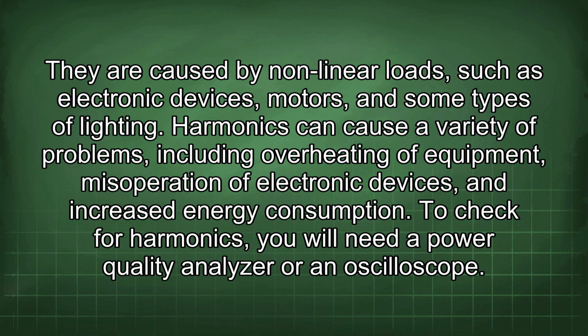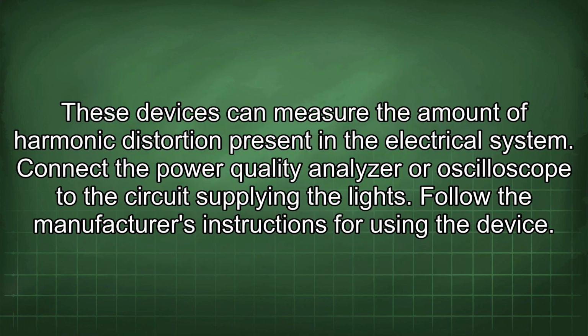Harmonics can cause a variety of problems, including overheating of equipment, misoperation of electronic devices, and increased energy consumption. To check for harmonics, you will need a power quality analyzer or an oscilloscope. These devices can measure the amount of harmonic distortion present in the electrical system. Connect the power quality analyzer or oscilloscope to the circuit supplying the lights. Follow the manufacturer's instructions for using the device.